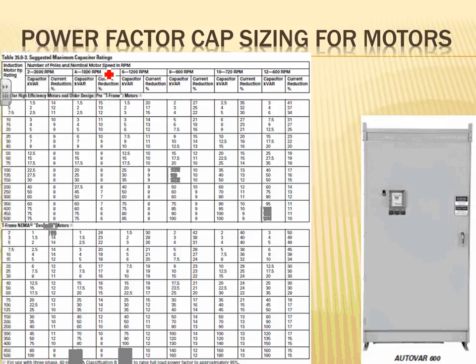So here's an example. The most common motor typically is my 1800 four pole. 1800 four pole, they'll give you 1750 RPM. 1800 RPM four pole. Sizing a capacitor here for you. Let's just say we have a big boy, a 50 horsepower motor. These are horsepower. And I want to size the capacitor for that baby. I can size a 10 kVAR right next to that offender and tie it to the load side of the overload, and that will offset and correct the power factor, I believe they go here between 92 to 97, depending how loaded the motor is. So that correction will take you from 92 to 97. That's exactly where I want to be.